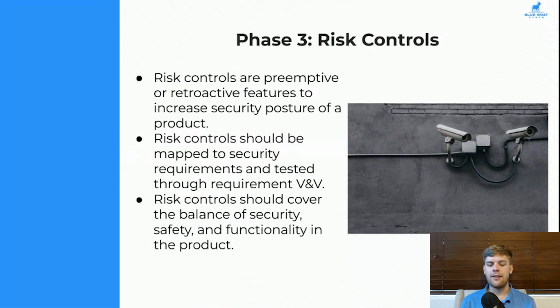If we have an easy example for a password field, we typically recommend that you have a sufficiently complicated password. So this is going to be lower and uppercase letters, numbers, special characters, all in a combination, and at least 12 characters. Of course, that is going to be less secure than all of that for 20 characters. However, it's likely going to be very difficult for a user to remember 20 characters. And so then we're running into a risk of them putting a sticky note on the device to try to remember it, or just using something very simple so that they don't have to try to remember a complicated password. And so there's always going to be a level of balance here when we're implementing risk controls.